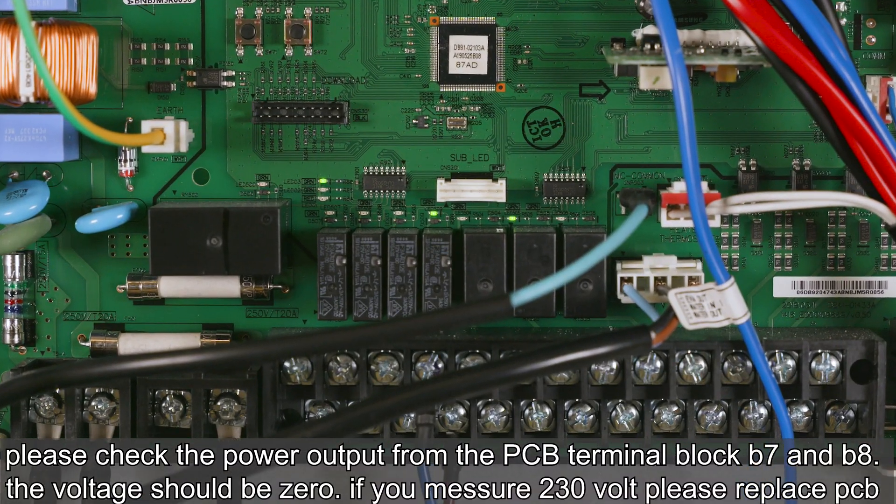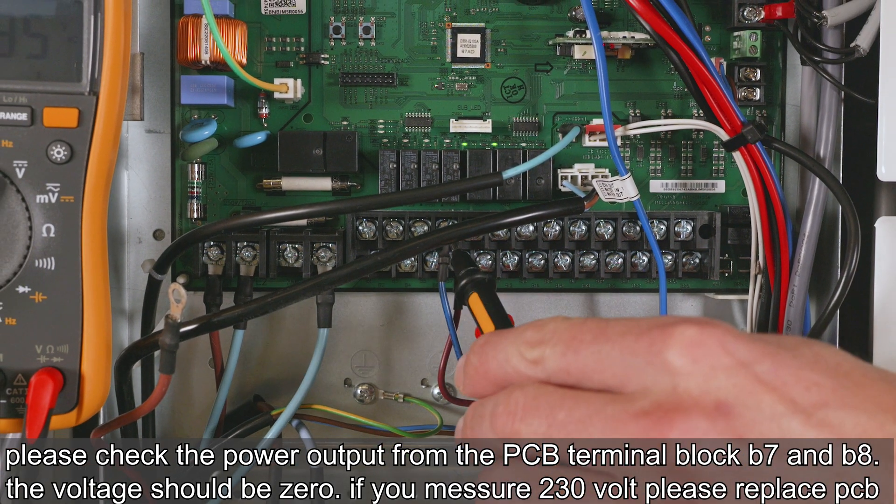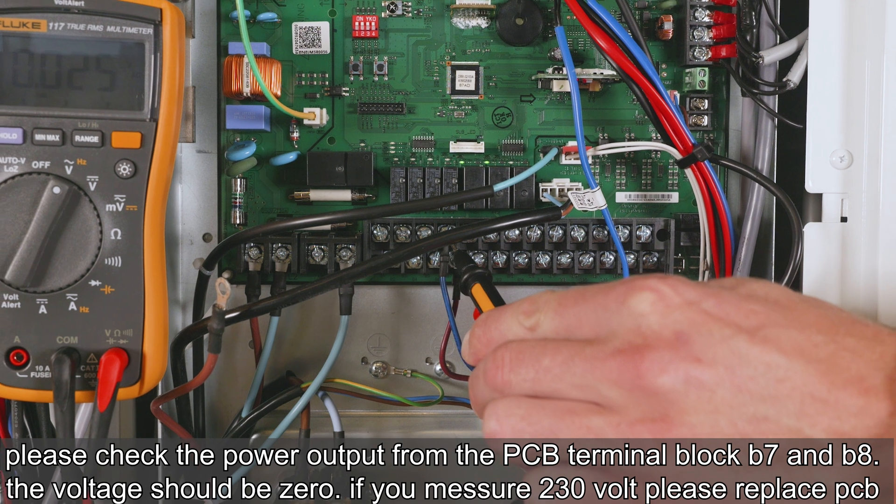Please check the power output from the PCB terminal block B7 and B8. The voltage should be zero. If you measure 230 volt, please replace the PCB.